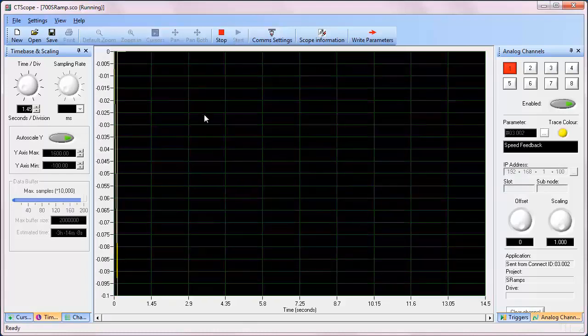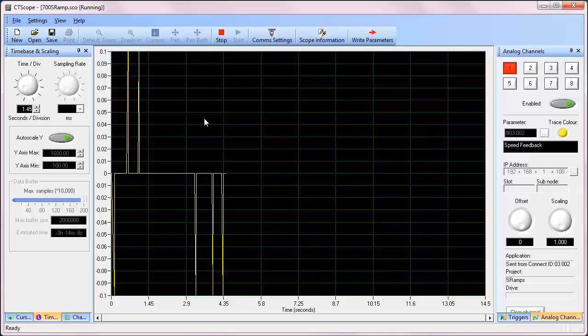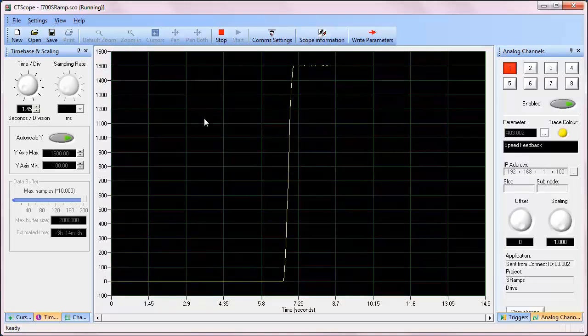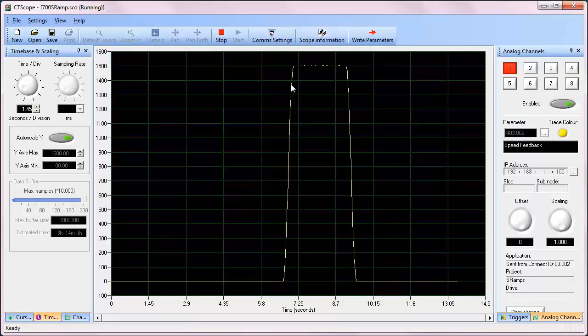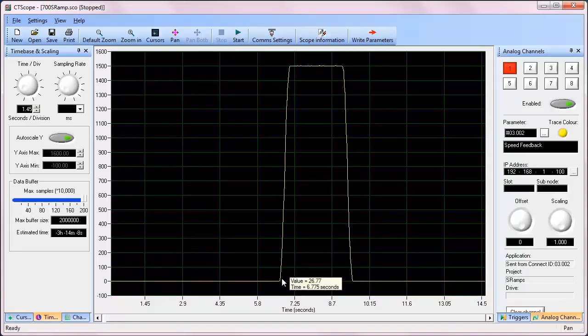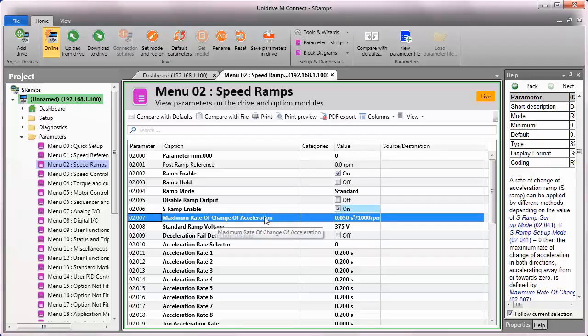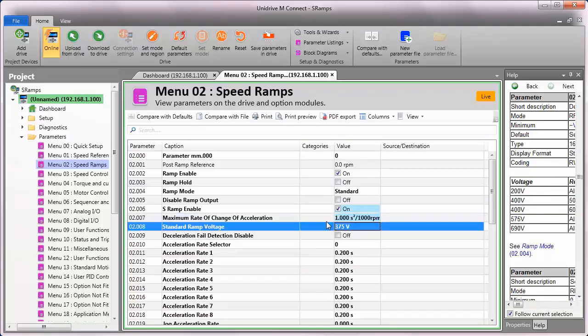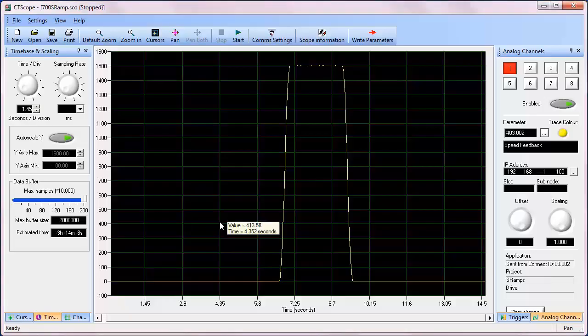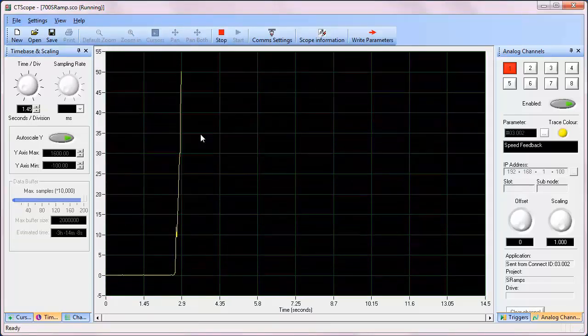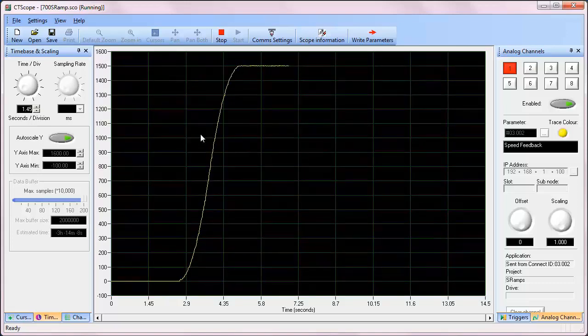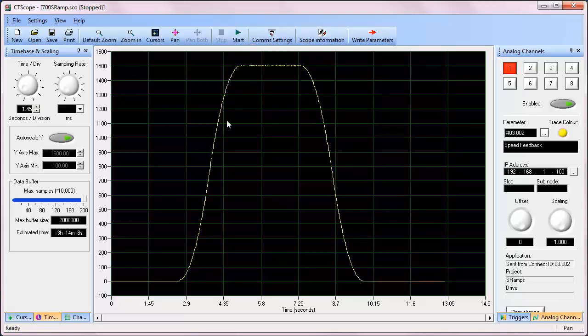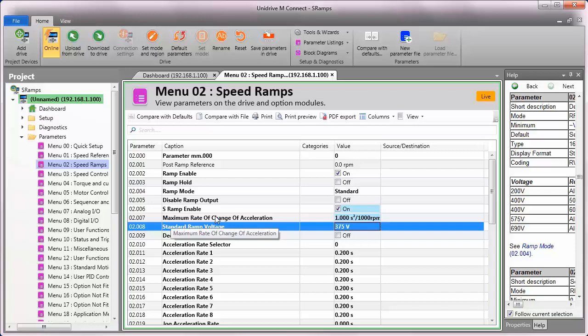So let me move over to here and I will start my trace. And this is what it's going to look like using the default settings. So as you can see, that's not much of an S. Very, very slight amount of curvature to these transition areas. But if I want to make that larger, I'll just increase my limit here. And I'll bump it all the way up to one second here, so we have a very definite, noticeable change. And then I'll go back to CT Scope and we'll do another plot. Now when I run the drive here, you can see a pretty dramatic change in the shape of those S portions or the transitions. So single mode then, to summarize, uses a single limit programmed in parameter 7 as the maximum amount of change of acceleration during those four transitions.